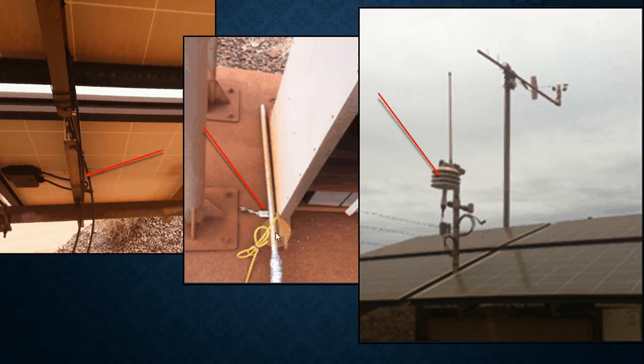If time permits, seal off the ends of the inlet tube with plastic bags. That would stop water from going in, so when we need to start the station up again we don't need to clean the inlet. The picture on the right shows that after all sensors are removed, the atmospheric temperature sensor is to be left intact and made sure it's facing upright.